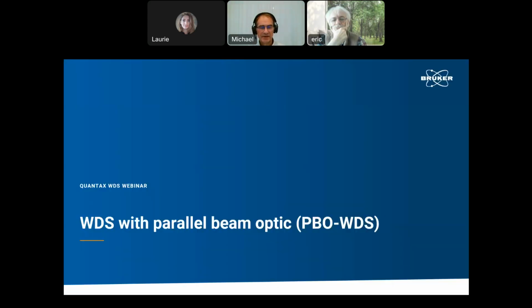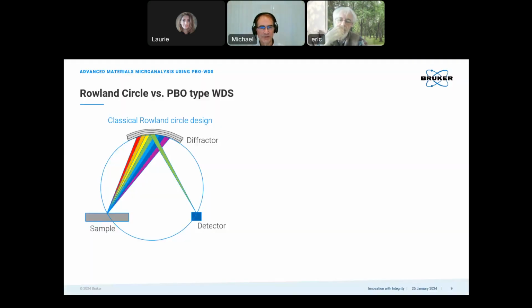Now let's have a look at some more advanced WDS systems using an optic, a parallel beam optic. So we start with a classical system. This is a so-called Rowland circle system, where sample, diffractor, and detector are sitting on a so-called Rowland circle with a constant diameter. The system is guaranteeing that the focus point is always in the detector.